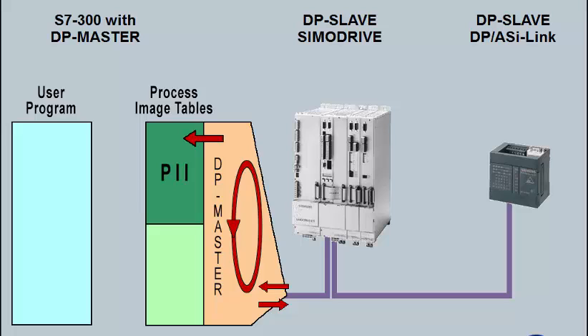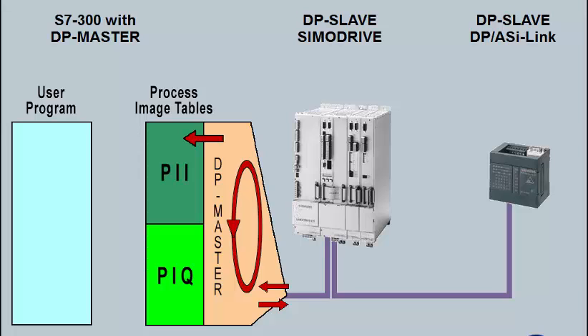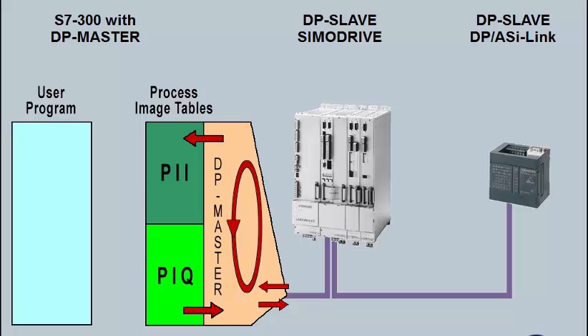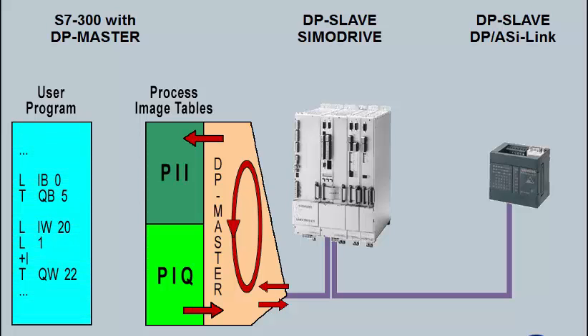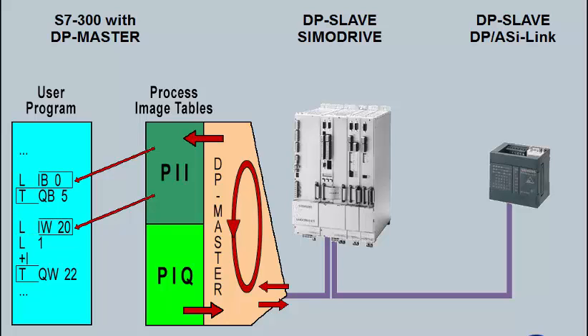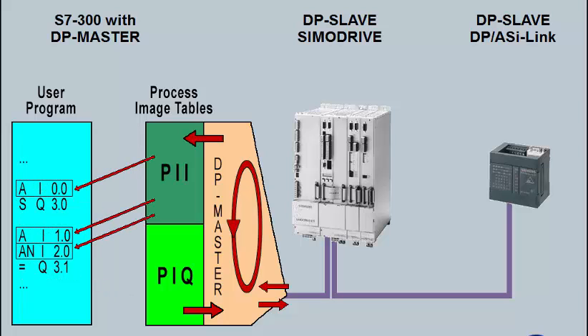After processing the input data, the results are written into the process image output table. From there, the output data are, after each user program cycle, transferred to the DP master. The access to the process images occurs per byte, word or double word by means of load and transmission commands or bit by bit using logic operations.